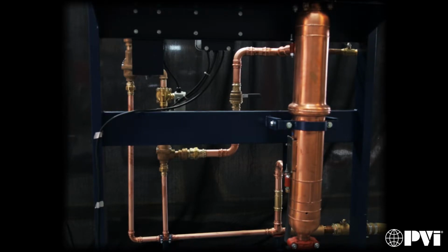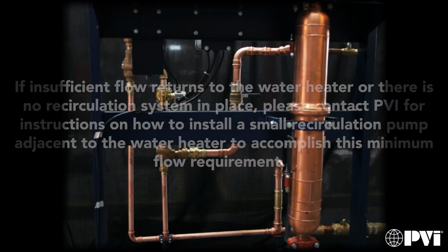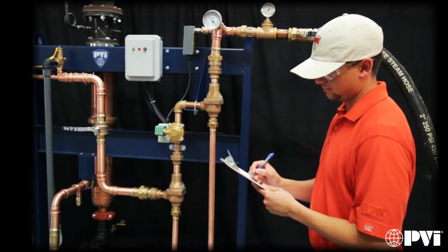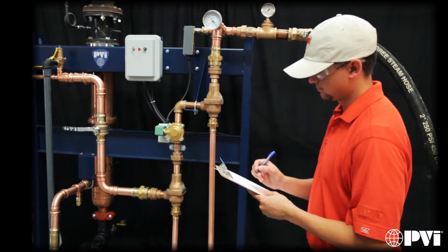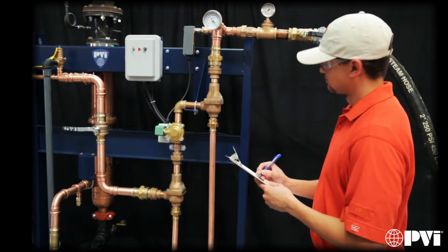Heat transfer will begin immediately and charge the hot water delivery system. Confirm the recirculation system water pump is flowing and returning water back to the water heater. If insufficient flow returns to the water heater or there is no recirculation system in place, please contact PVi for instructions on how to install a small recirculation pump adjacent to the water heater to accomplish this minimum flow requirement. For warranty purposes and your records, fill out the startup form completely, including product serial number and installation address.